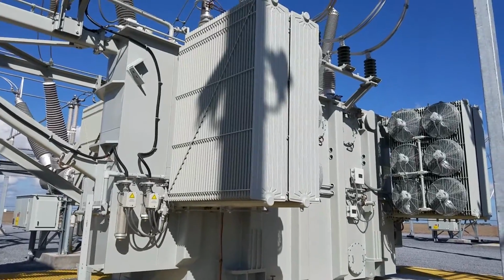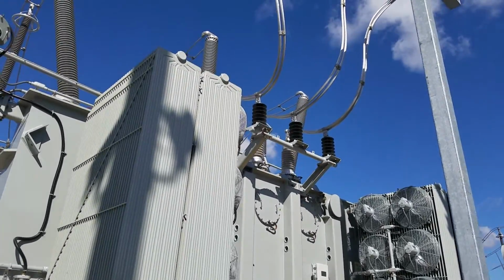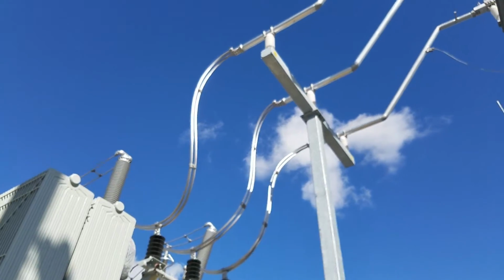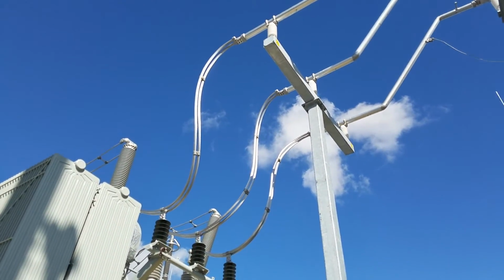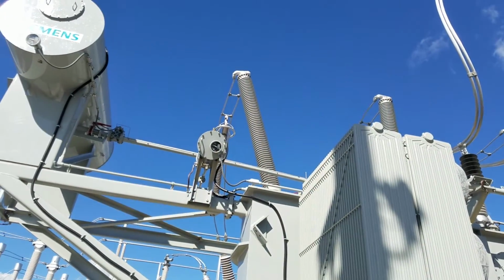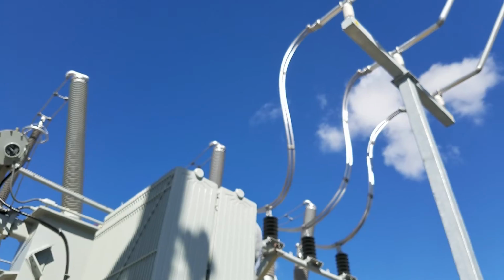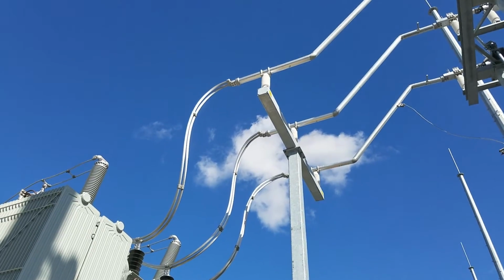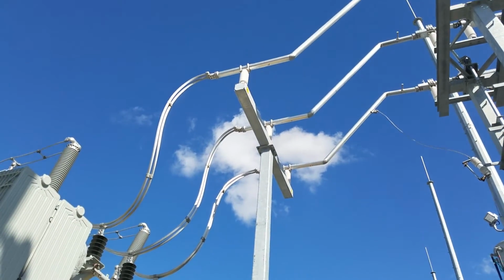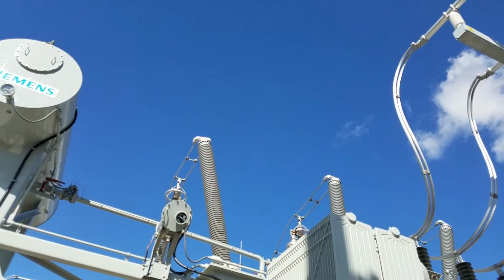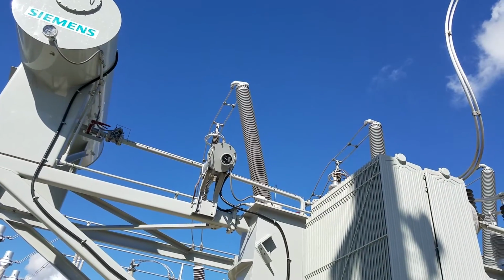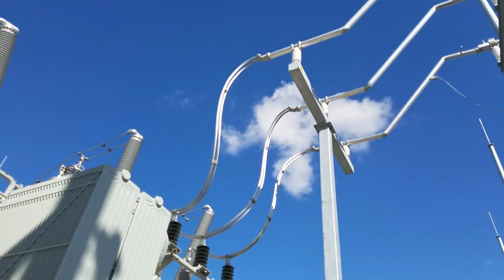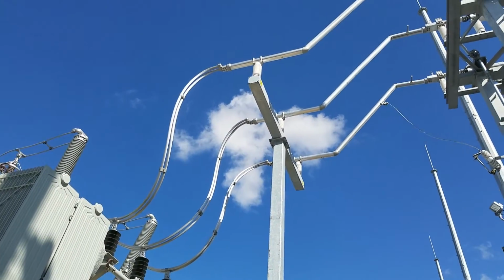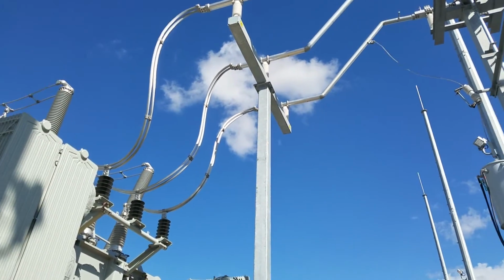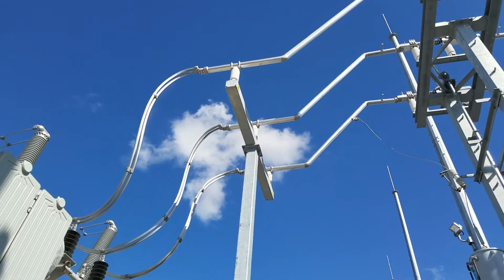Right, we're here at the substation still, going over the 34,500 volt side. You notice the cables are thicker on this side as opposed to the high voltage side, so probably doesn't make sense, right? You need the bigger cables over there. Well, no you don't. The lower voltage you go to, the higher the amperage. Say you're using 100 amps on the high side, I don't know the ratio off the top of my head, but you'll have, you know, 1,000 down here on the low side. The lower the voltage, the higher the amps. So that's why you have thicker cables on the lower side.